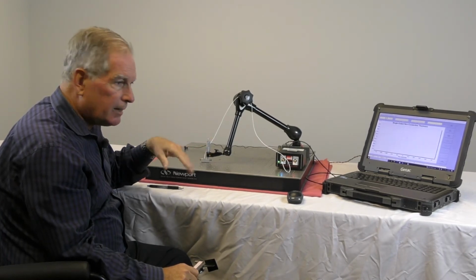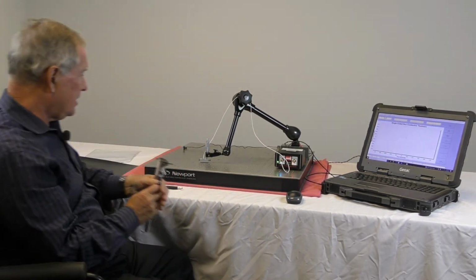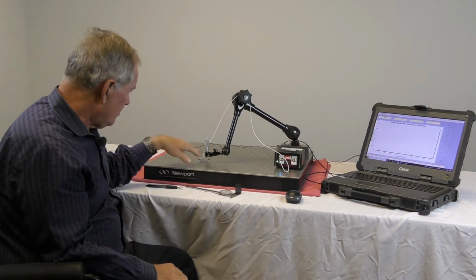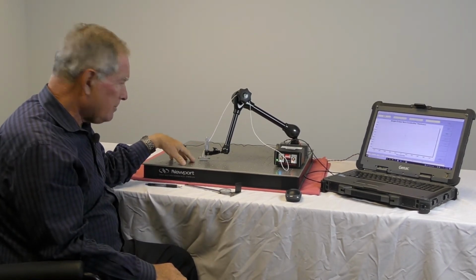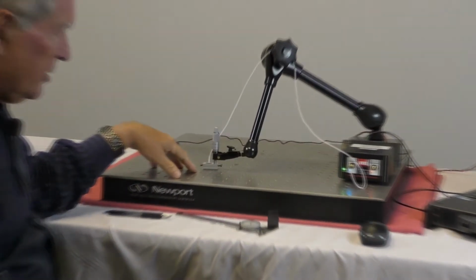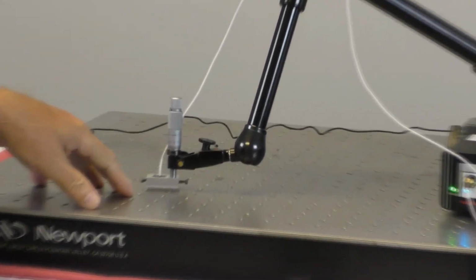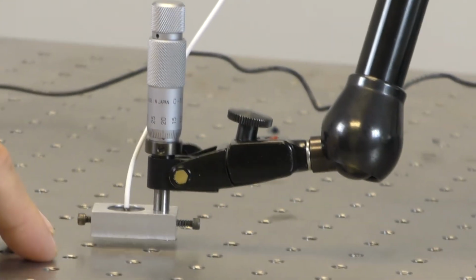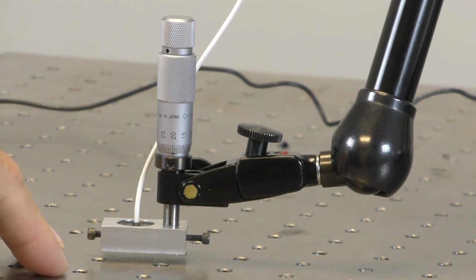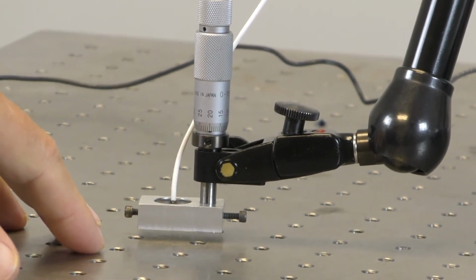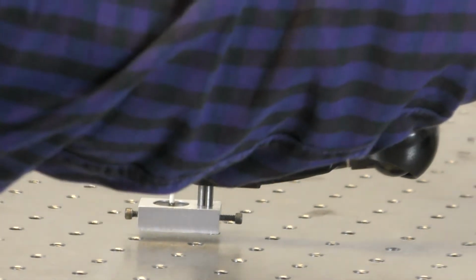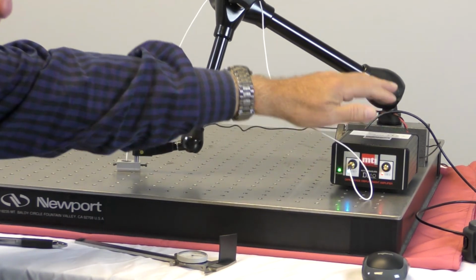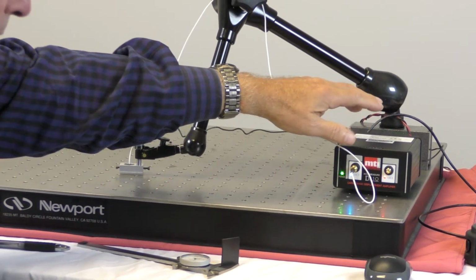Once you get the hang of it, you can do it in less than a minute. So we set our probe height above the ground plate. This probe is an ASP 1250M. What does that mean? It means it's 1.25 millimeters measuring distance, but we also have range extensions on the amplifier.